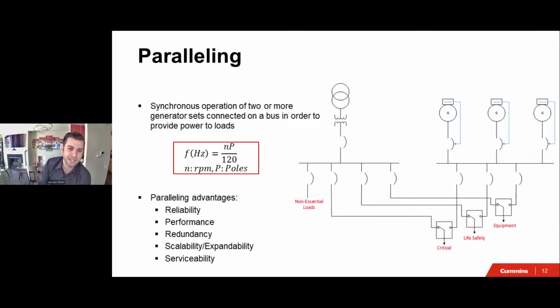Here you're looking at a one-line diagram of a very typical system of what's called an isolated bus. You have 3 generator sets, a few transfer switches, and here is the utility. By the way, in this presentation, we're assuming that you've made the decision to parallel gensets. So we will not discuss whether we need a generator, or whether we need to do paralleling or not. The assumption is that we need to parallel, and how do we achieve paralleling.